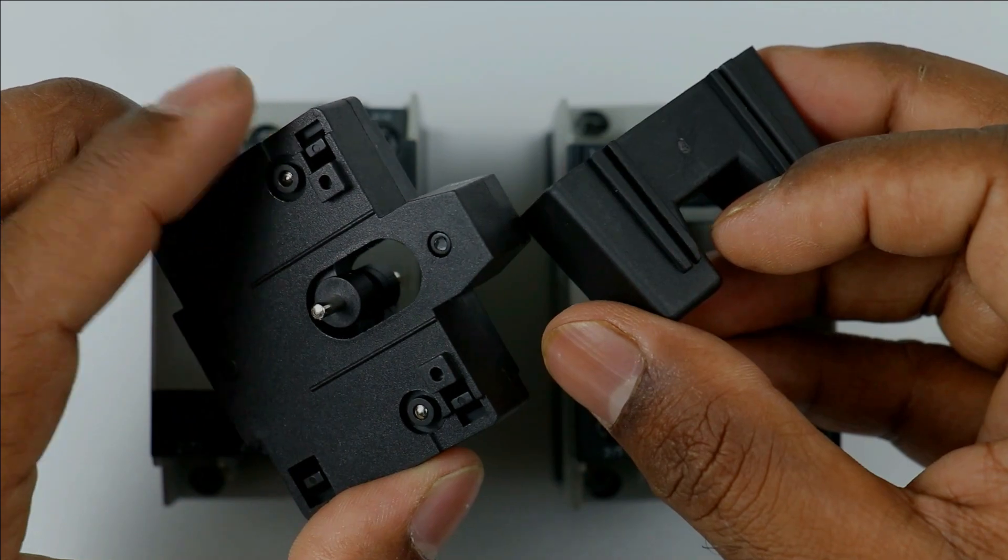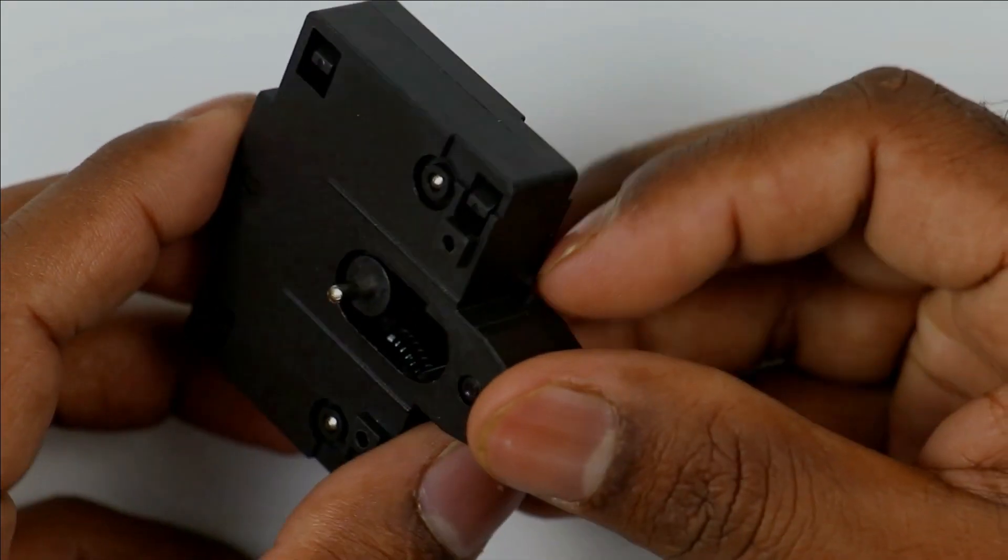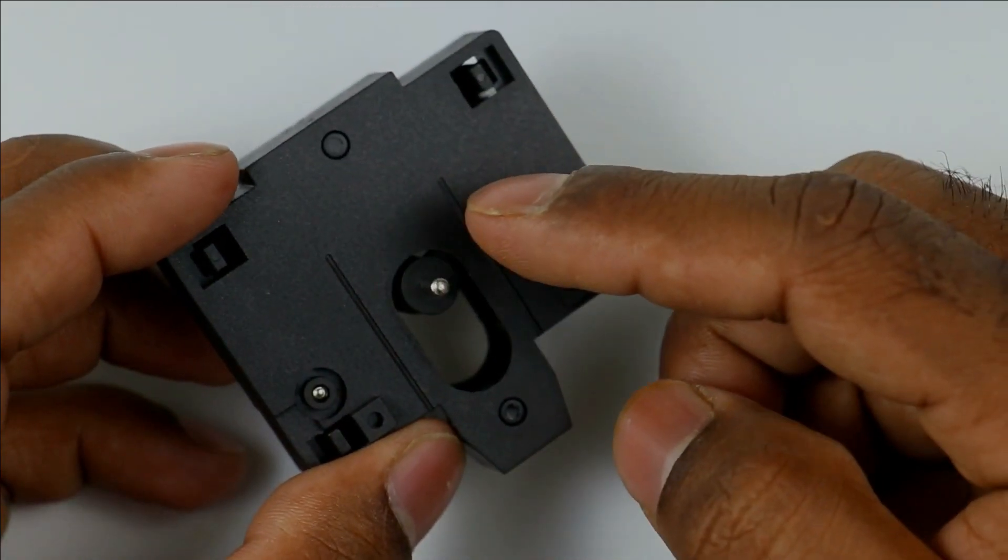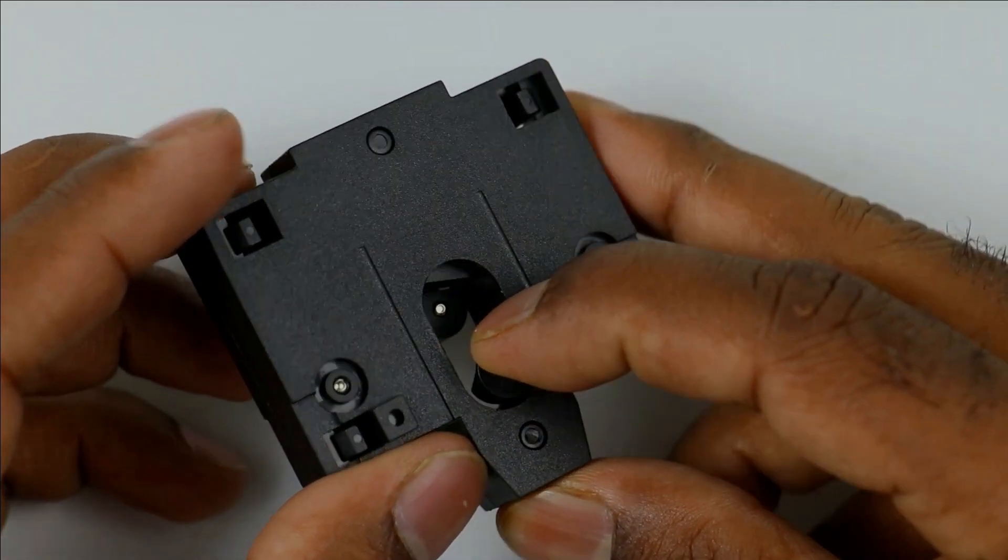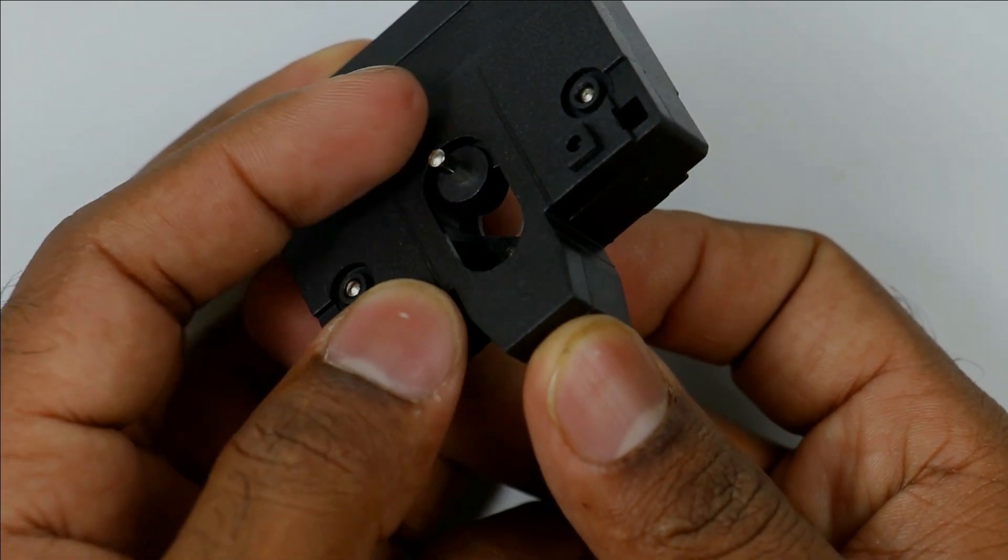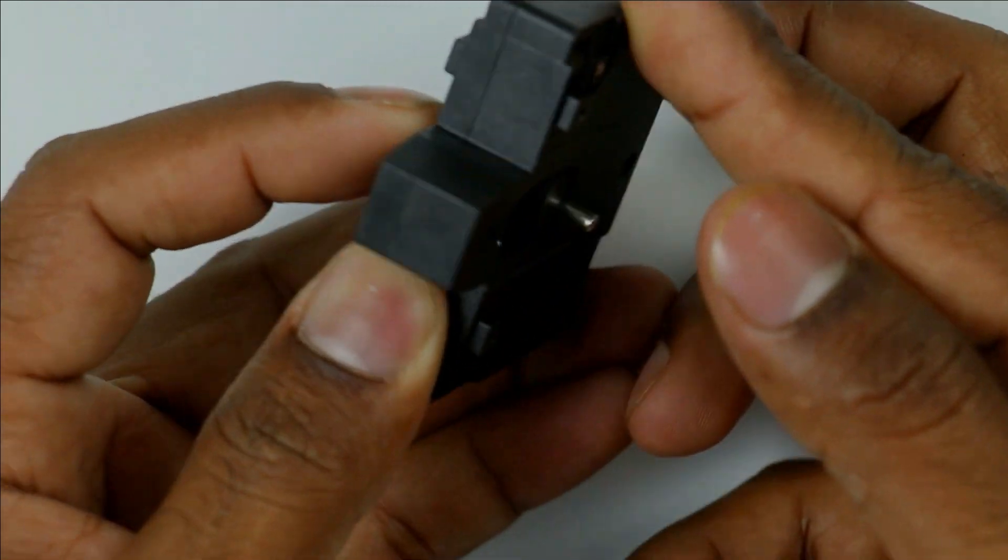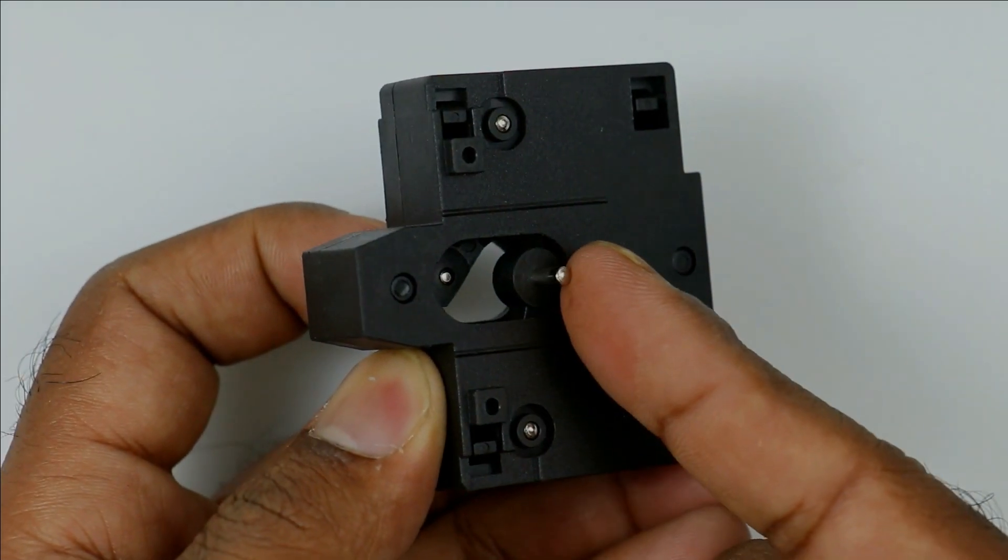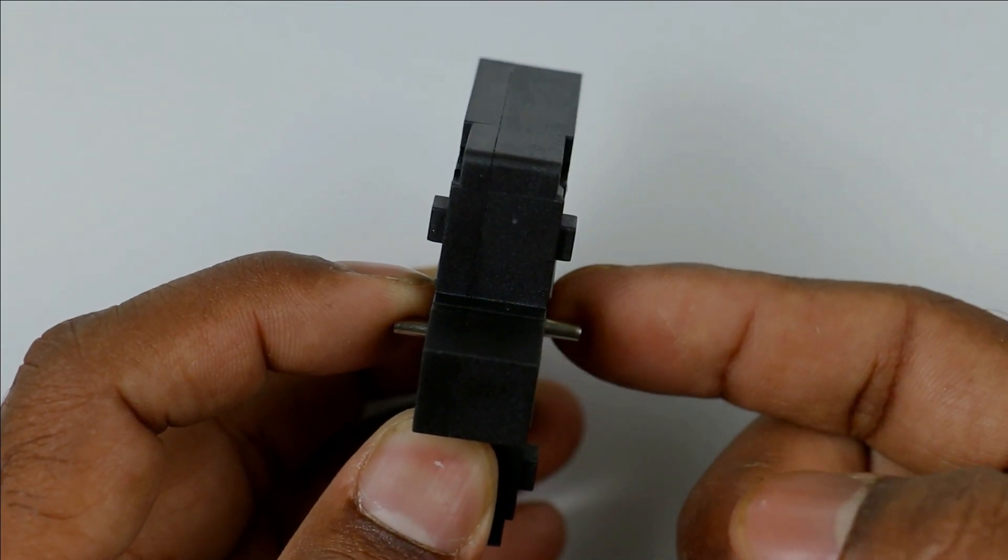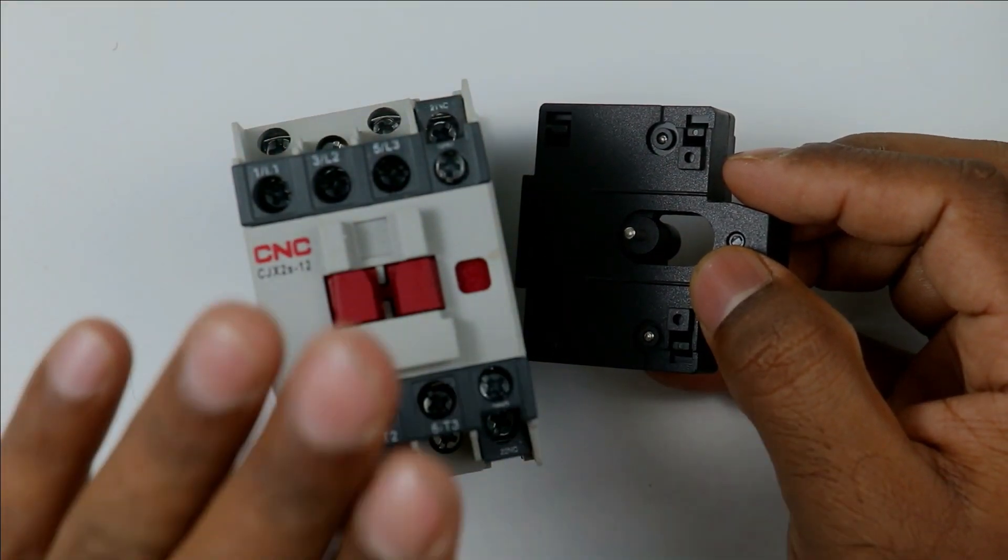To interlock these contactors, we have to use this type of accessory. This contactor interlocking which I have now has two plungers, one on this side and other on this side. If I try to pull this upwards, on the other side this lever or plunger will lock itself and not move upwards. Similarly, if I pull this lever upwards and try to pull this one, then it won't make full contact. Overall, we can say only one at a time can be pulled upwards. Now how this can be mounted with contactor, let's understand.